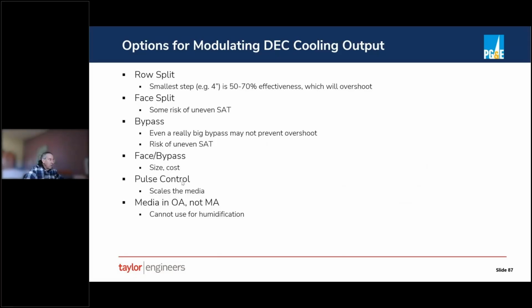Pulse control. So on that data center, we talked about the fatal flaw, what we ended up doing is instead of dripping water continuously over the media, we just dripped it in enough volume, basically like a chilled water valve. We modulated the water flow to get the supply air temperature. The issue there, of course, is that it scales up the media. The media is designed to basically be fully wetted. So you're usually running 3 to 4 times as much water over the media as you're evaporating so that it's always wet, kind of like a cooling tower. If you're just dribbling water, you get scale on the media. And so it basically plugs up the media pretty quickly. And so it ends up requiring that media to be changed out frequently.